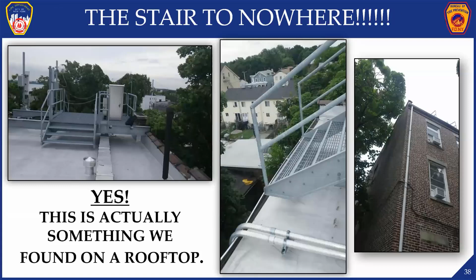Finally, there are some extremely interesting designs out there. This is what we call the stair to nowhere - something we actually found on a rooftop. Please use good sense when you design your installations. Just because there's technically a clear path from front to rear, side to side, doesn't mean it doesn't obstruct everything. We don't want stairs going off the side of the rooftop either. Just because it seems to match the code doesn't mean it's safe or good. Make sure common sense is injected into your designs, because we don't want people walking off the sides of rooftops because stairs were there.